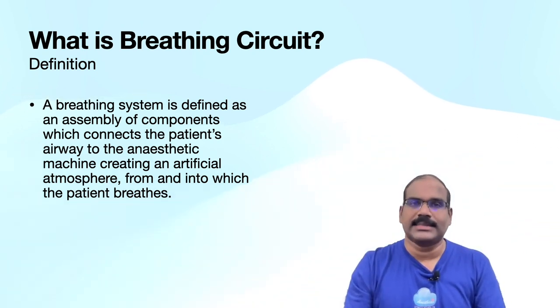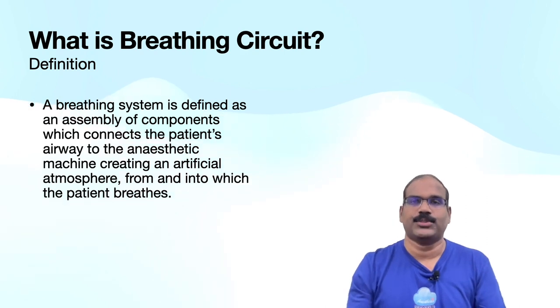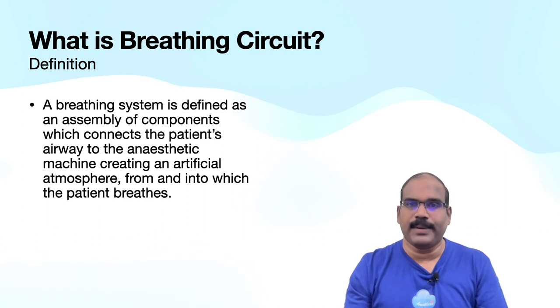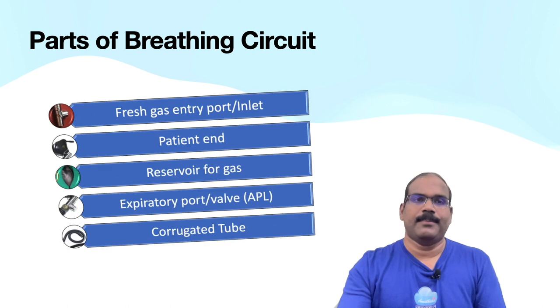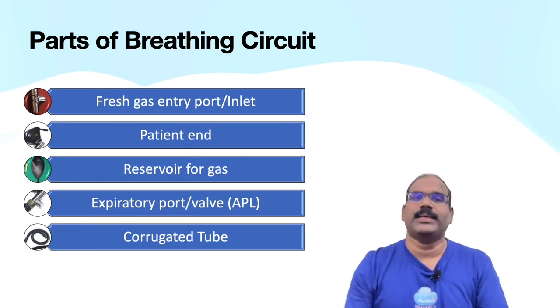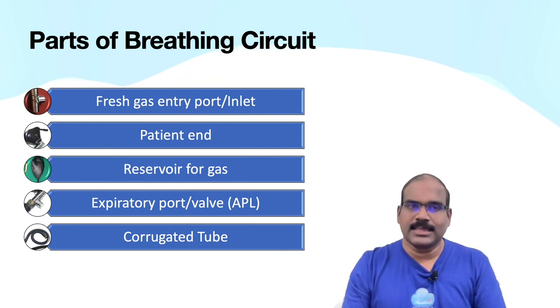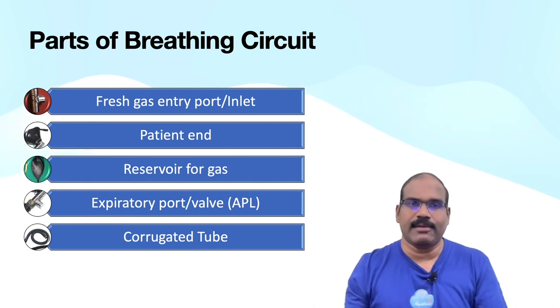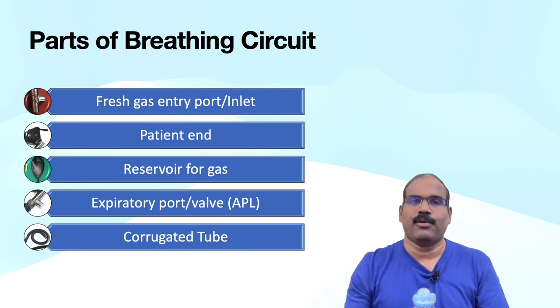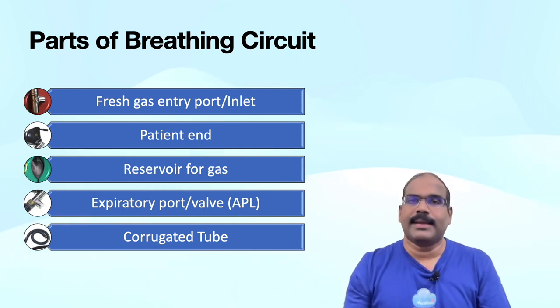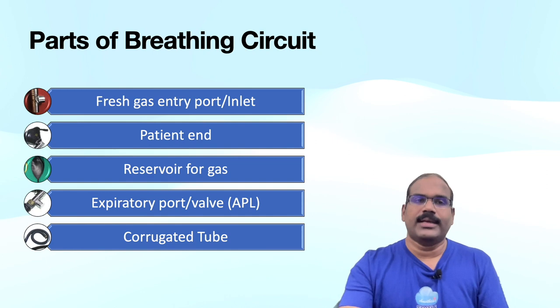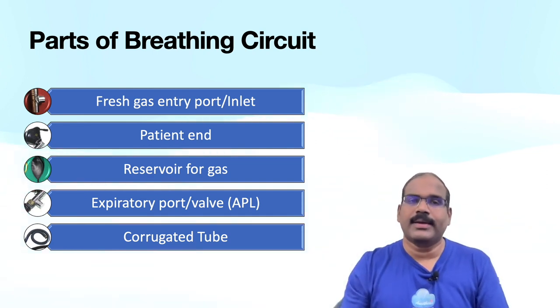What is a breathing system? A breathing system is defined as an assembly of components which connects the patient's airway to the anesthetic machine, creating an artificial atmosphere from and into which the patient breathes. A breathing system primarily consists of a fresh gas entry port or delivery tube, a port to connect to the patient's airway, a reservoir in the form of a bag or corrugated tube to meet peak inspiratory flow requirements, an expiratory port or valve through which exhaled gas is vented to the atmosphere, and corrugated tubes for connecting these components.